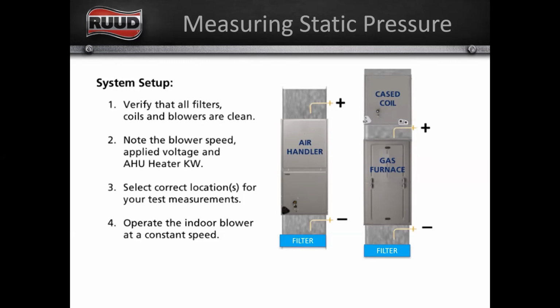And as far as placement goes, let me expand on that a little bit, because you're always going to have some friction and some turbulence in your airstream. And so when we put together the blower tables and we're measuring static, we are traversing the duct. And really what that means is, an example, like both of these pictures that I have on the screen, we wouldn't be taking one measurement. We'd be taking at least 9 measurements, right? So we've got sort of an array of static pressure hoses and tubes where we've got 9 points in that airstream that we're measuring. Now, is that what I'm telling you that you have to do? No, not necessarily.